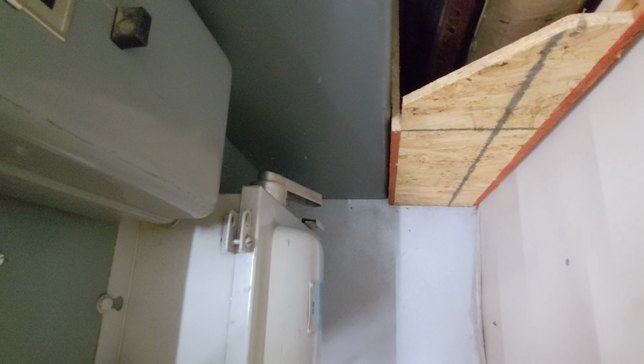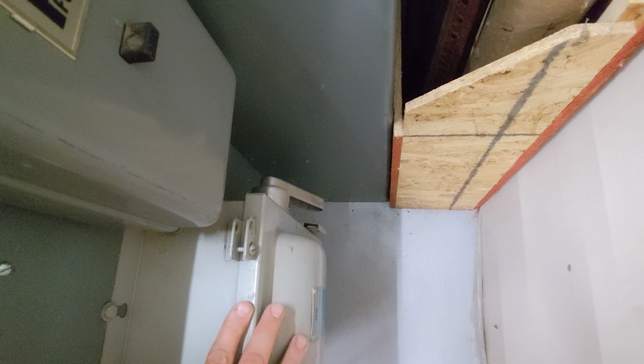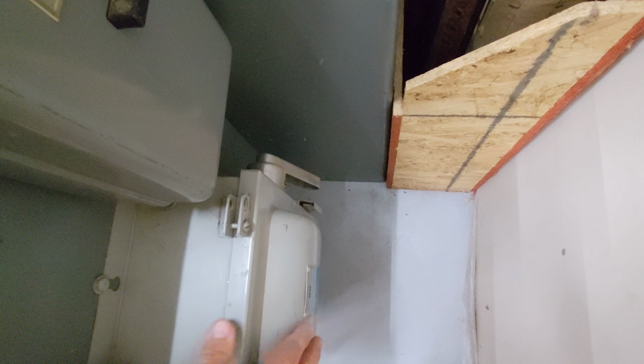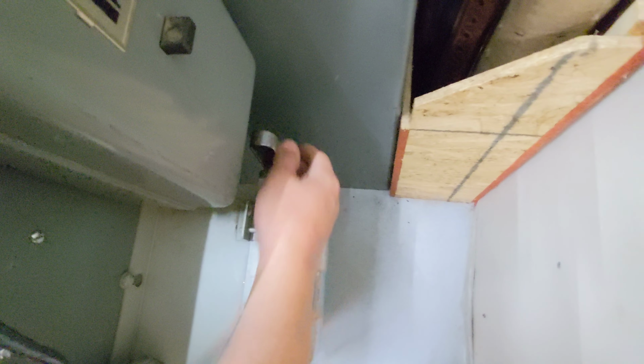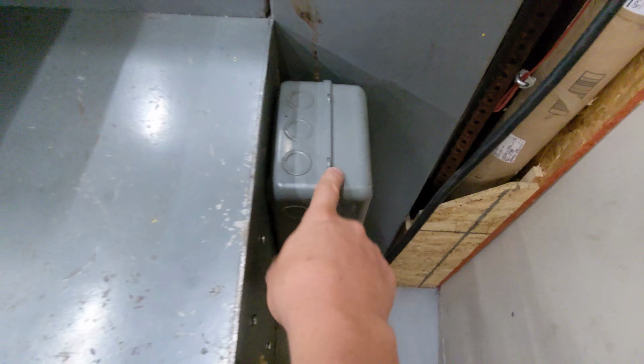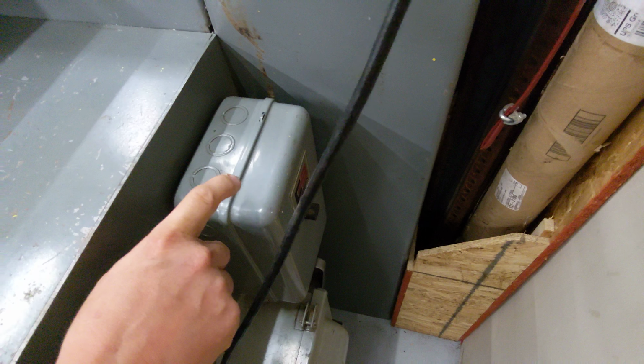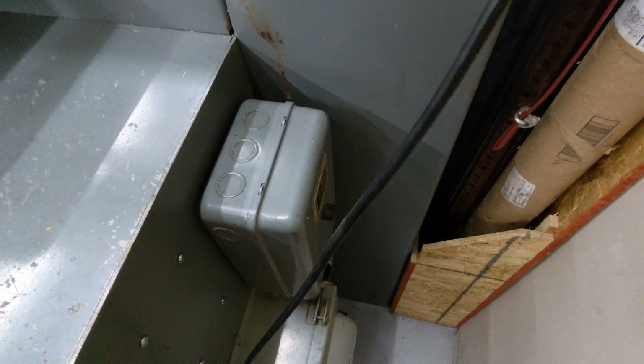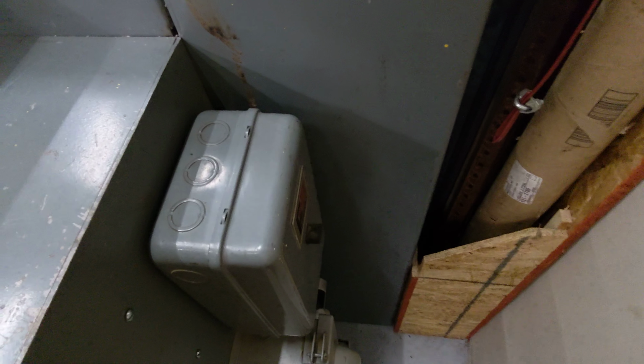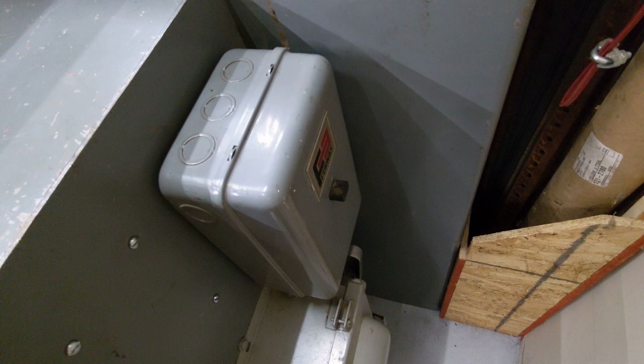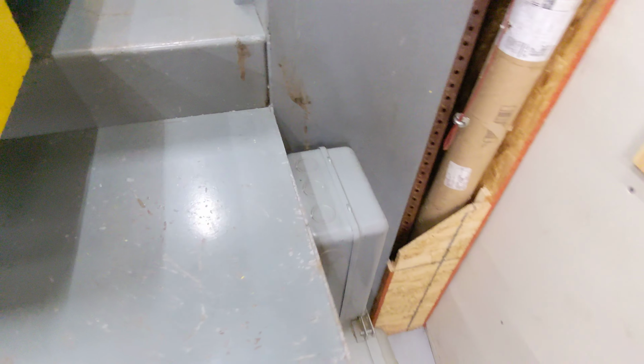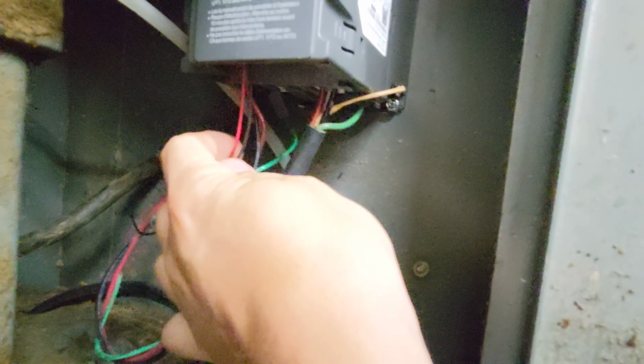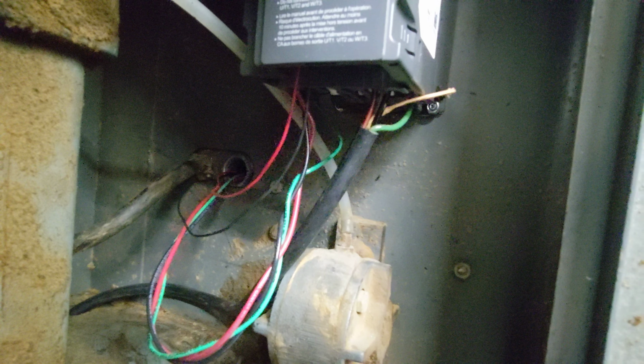So now the VFD won't have power. The whole thing is off, cold, no power coming past this, kind of like it would be in the original configuration. So with power on, there's now power into this motor starter. But because we don't need the motor starter as a motor starter anymore, I wanted to effectively use it as a latching relay for the low voltage inputs to the VFD. Like many VFDs, this takes low voltage inputs for forward, stop, and reverse. In this case, I just need forward and stop, which is opening and closing these two contacts.